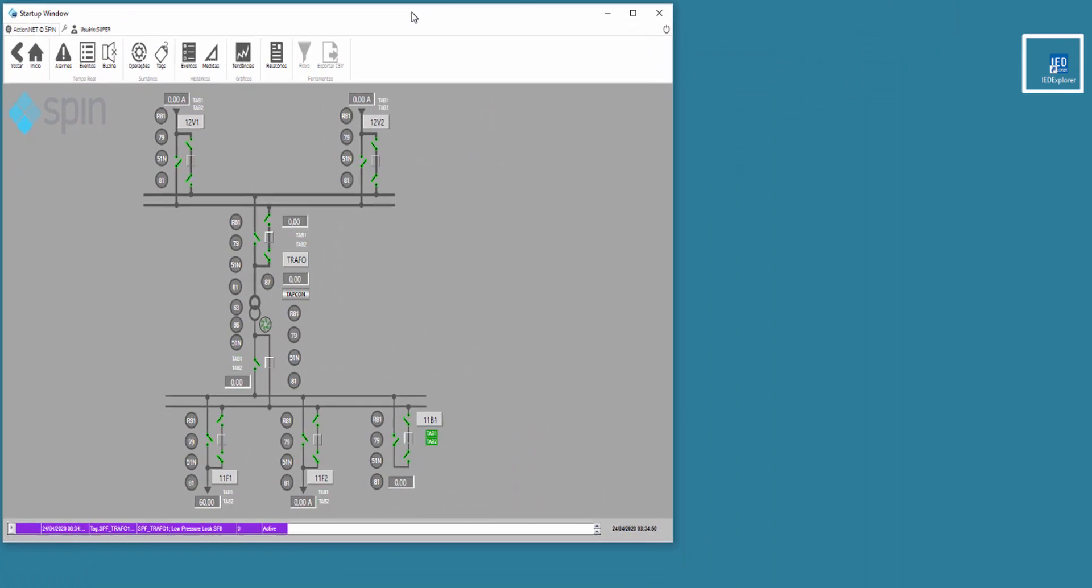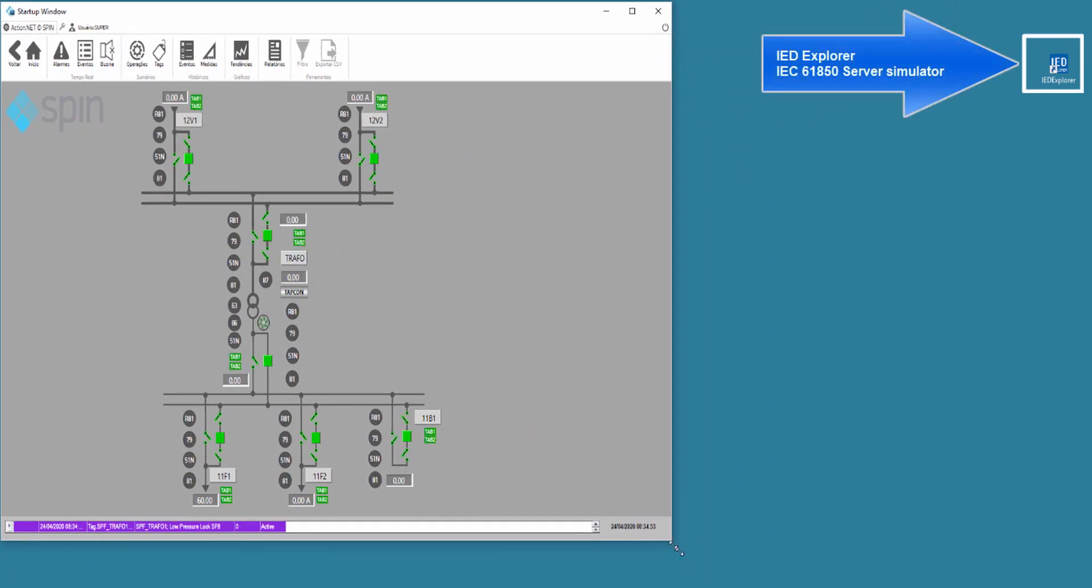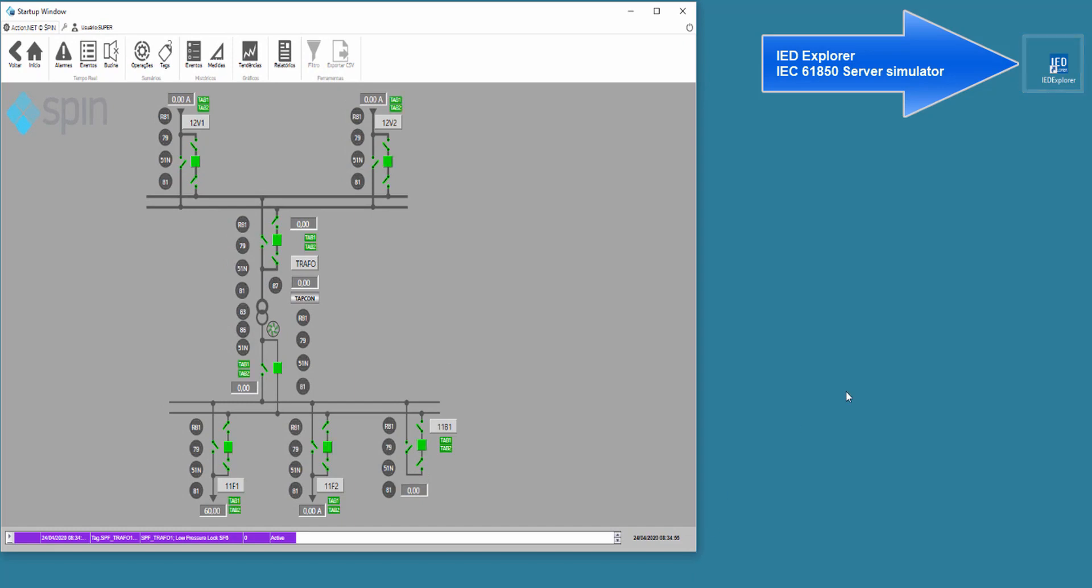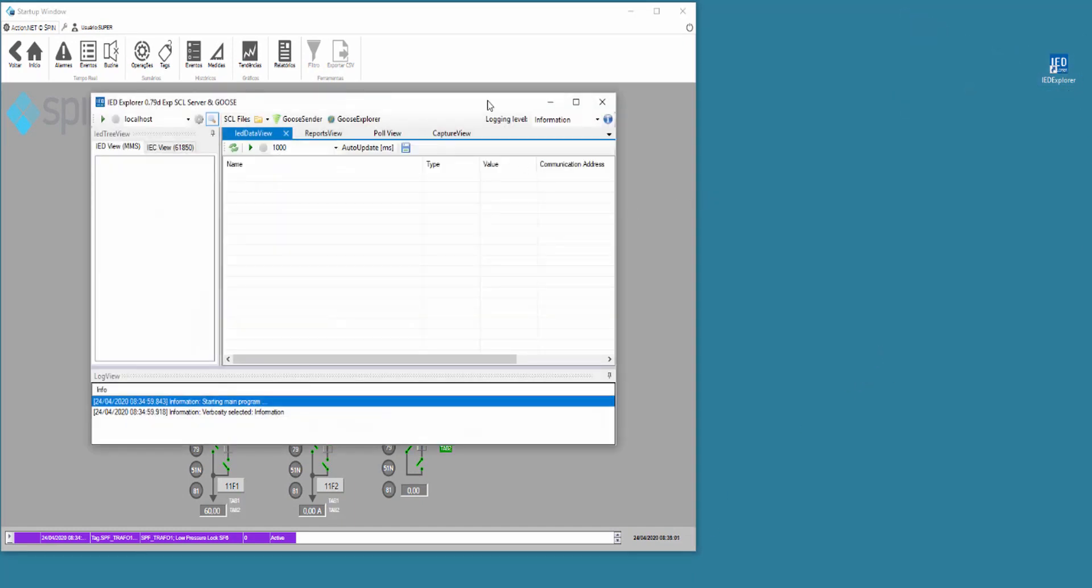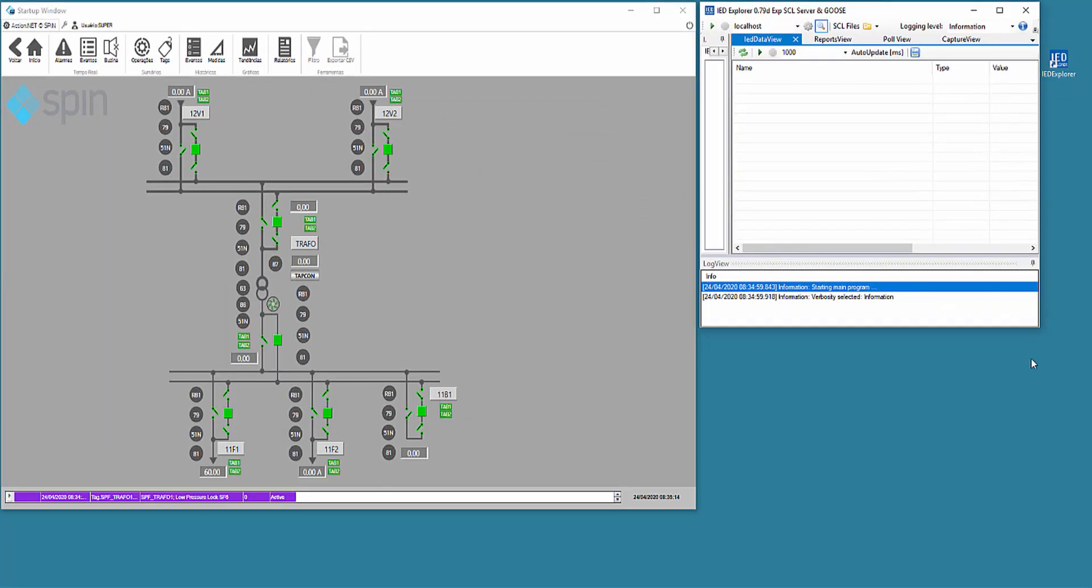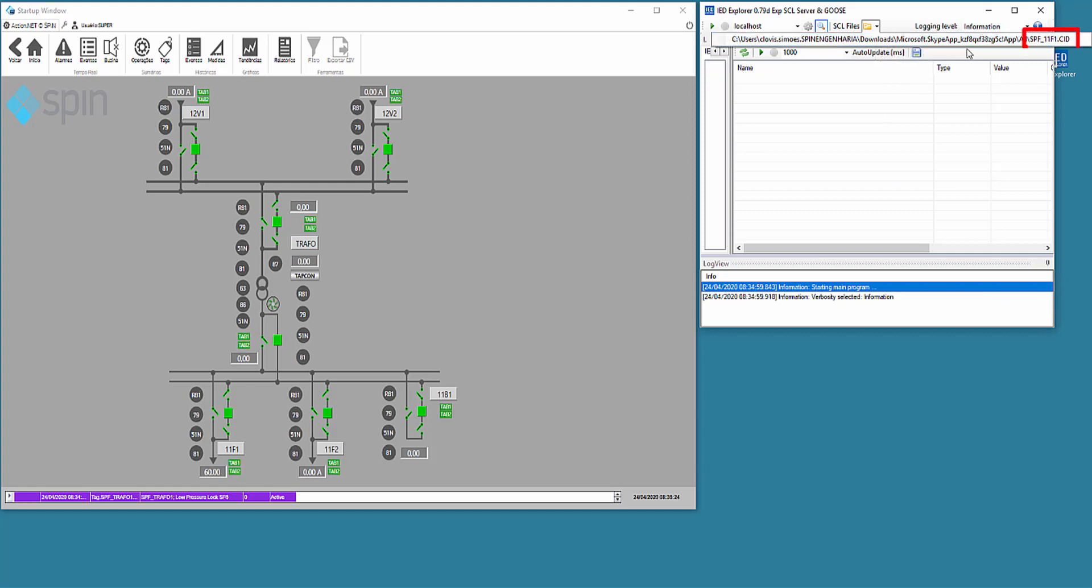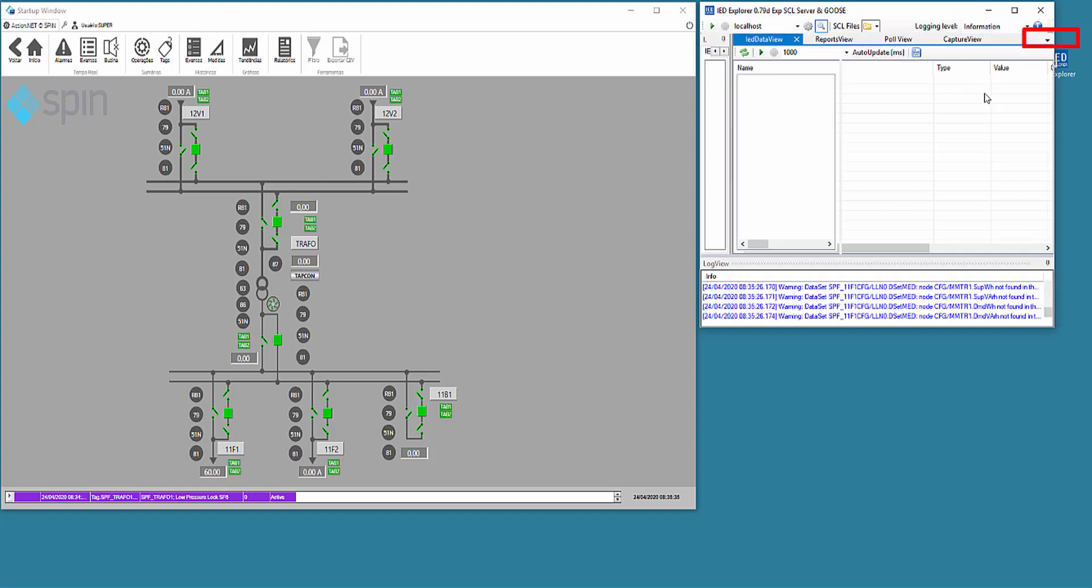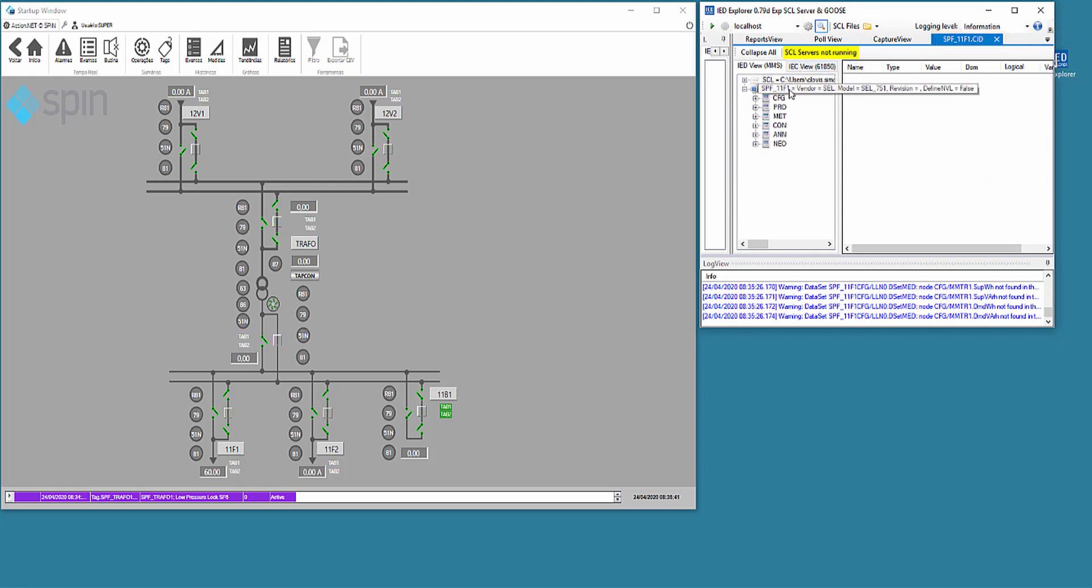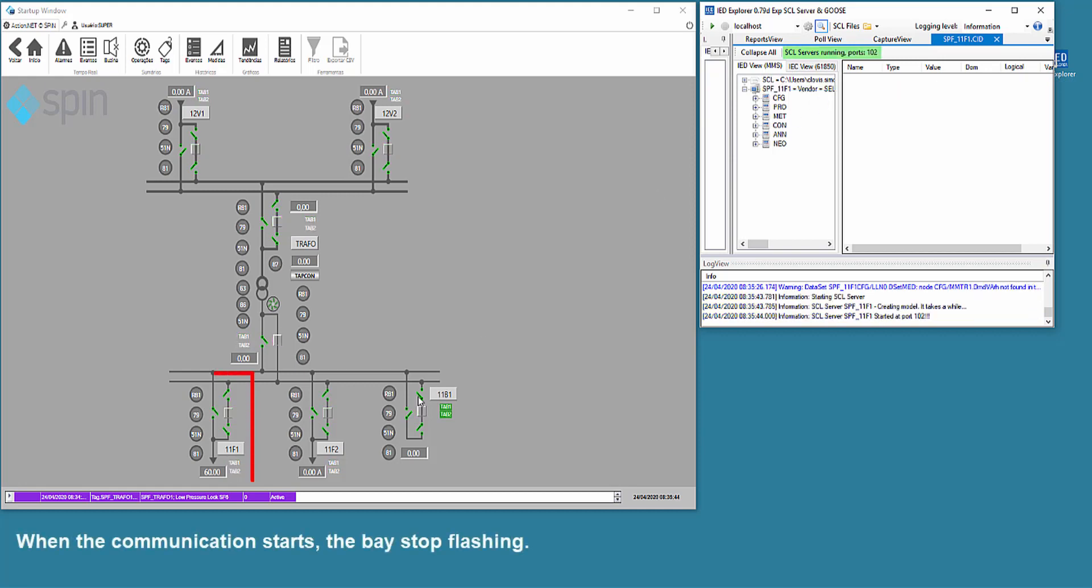We will run the IED Explorer program, that can function as an IEC 61850 server. We will load an ICD file from the protection relay of 11F1 feeder bay. Once the simulator starts the communication, the bay stops flashing.